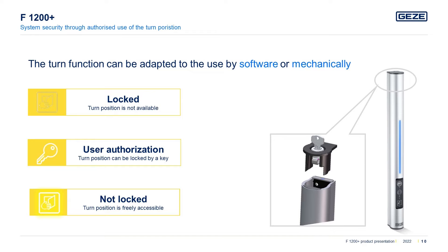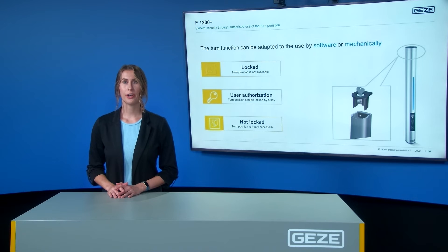If the window may only be turned by authorized users to ensure safety and building security, the turning position can be blocked by software or mechanically. This is especially useful in multi-story buildings such as hotels, offices, and public buildings. If the turn position is software-blocked, the button with the turn icon is not lit up, indicating that this function is currently not available. The turn position can also be blocked mechanically by means of a lock on the drive and a corresponding key, allowing the janitor or facility manager to release it if required.